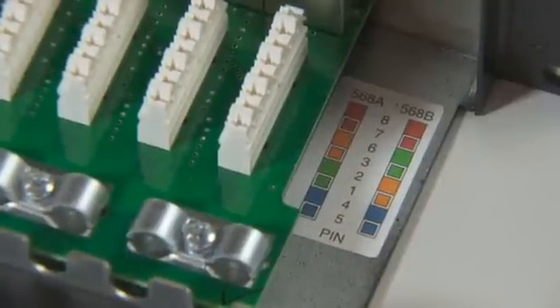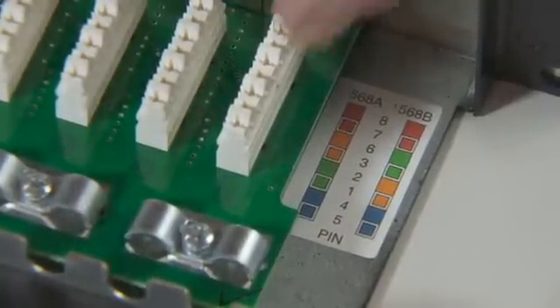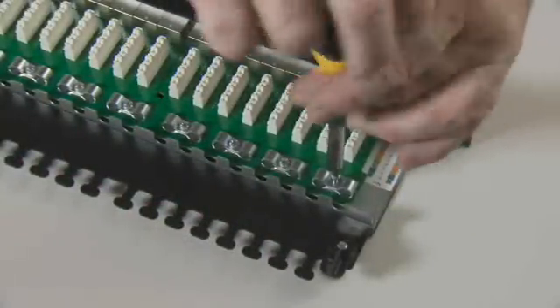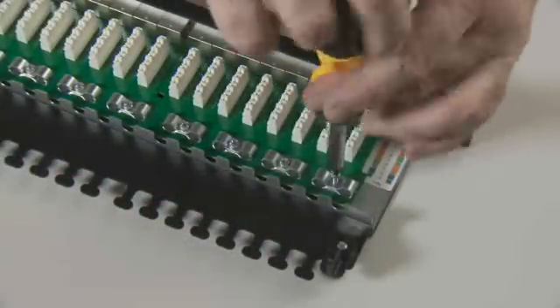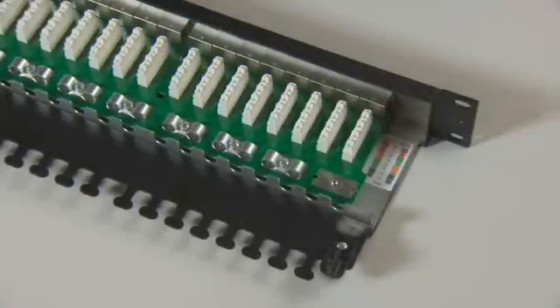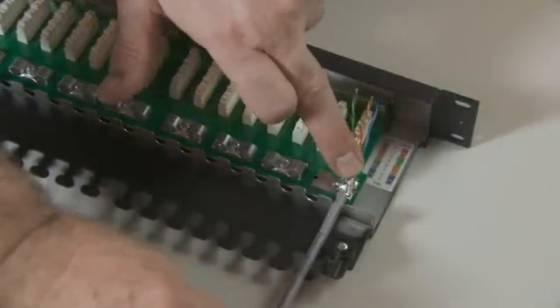To maintain the integrity of the shield within the cabling system, we need to ground the shields of the cable to these grounding clamps. Starting from right to left, line the cable up with the management bar and the leading edge of the IDC block.